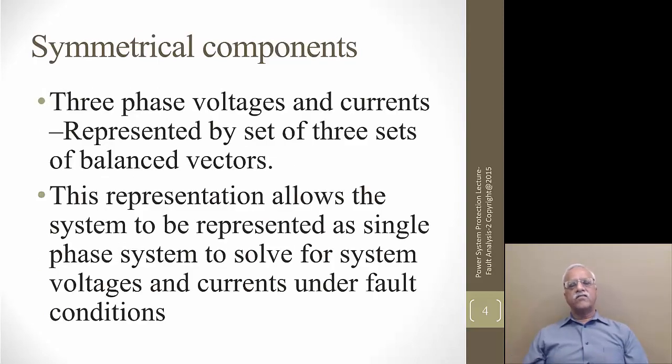Okay. And now we said that it is invariant of the voltage. The 8 per unit continues if the current of 800 amps is generated and flows up to 230 kV and continues. It stays 8 per unit. So it does not get into actual amps and volts. We avoided representation with a simple network without taking into account different voltages. We are just representing in per unit impedance and per unit quantities, so it gets rid of these various voltage levels.